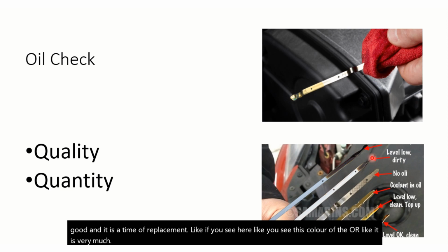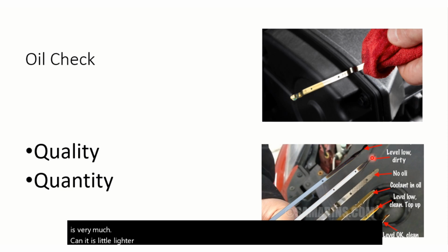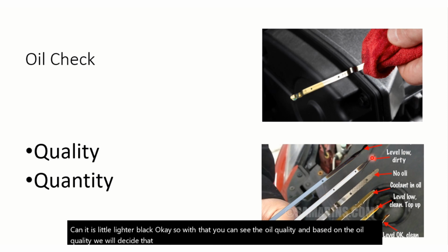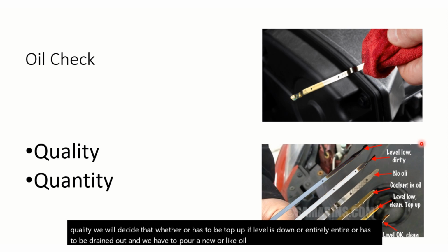a little lighter black. So with that you can see the oil quality, and based on the oil quality we will decide whether the oil has to be topped up if the level is down, or the entire oil has to be drained out and we have to pour new oil, like oil replacement. So this is what we have to do.